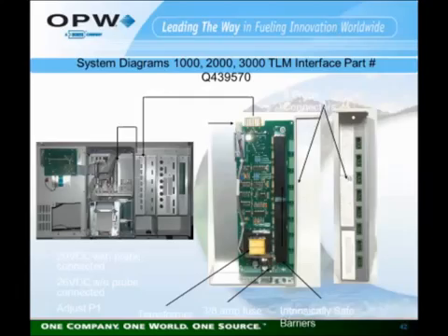On this module is an internal power supply that supplies the 26 volts DC power for probe operation. That voltage is adjustable, and there is a fuse for that power output to the probes. This has no relation to any other power in the unit. This is separate power for the tank probes only. It does, however, output a 12 volt DC voltage that is not used by the tank monitor portion of the unit, but is monitored by the main processor board. That 12 volts is compared to the 12 volt output of the main power supply, and if a difference is seen between those 2 voltages, then the main processor board will issue a trouble code to indicate a probe voltage problem.